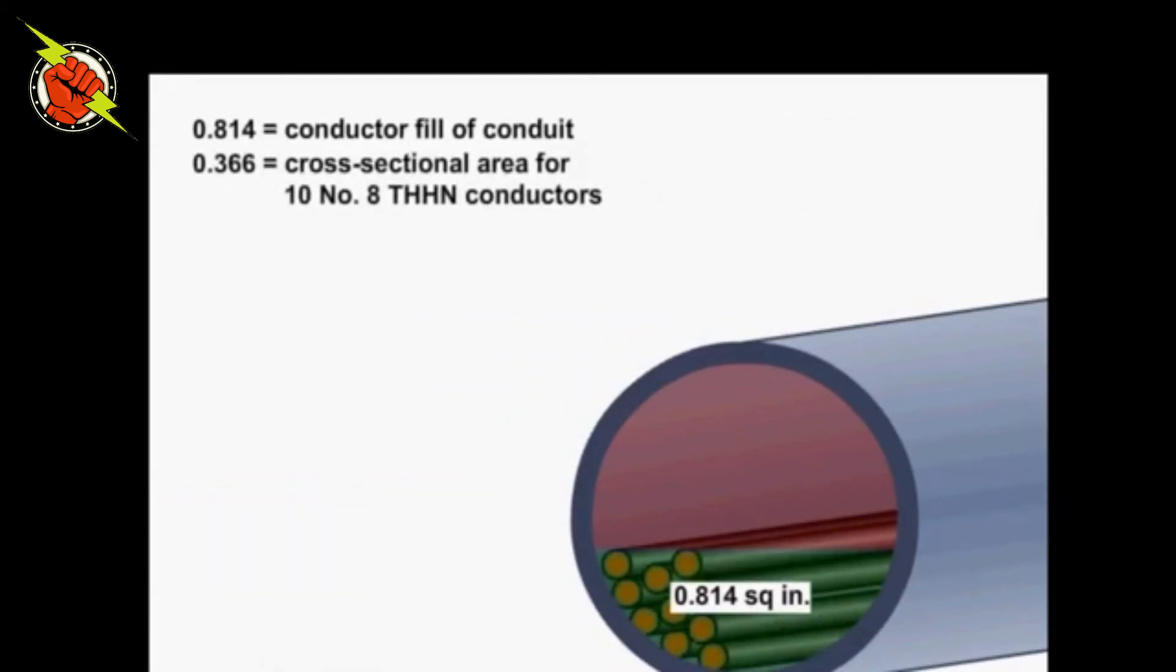Step 3. Determine the cross-sectional area available for additional conductors. Subtract the cross-sectional area of the pre-existing conductors from the conductor fill of the conduit. The cross-sectional area available for additional conductors equals 0.448 square inches.